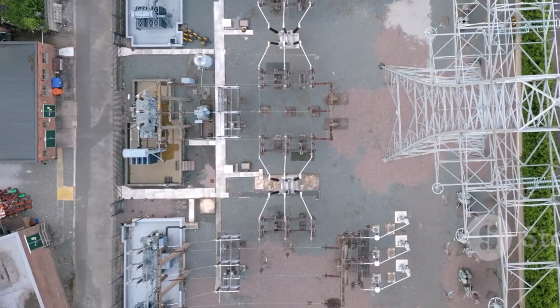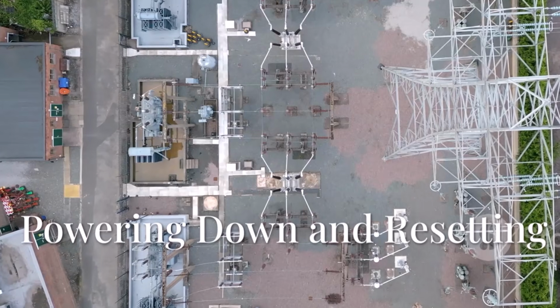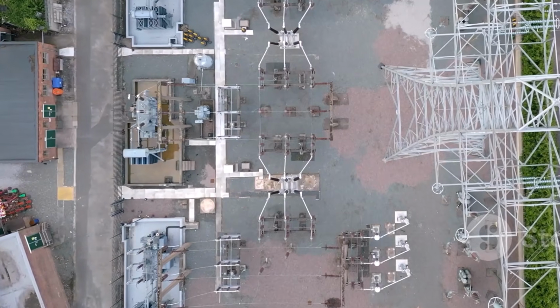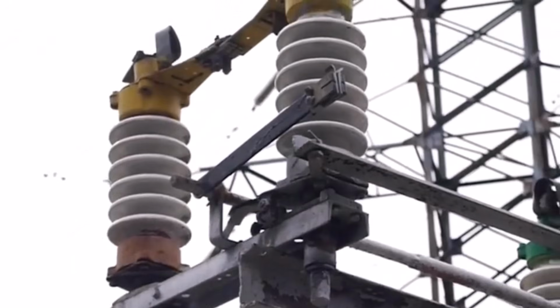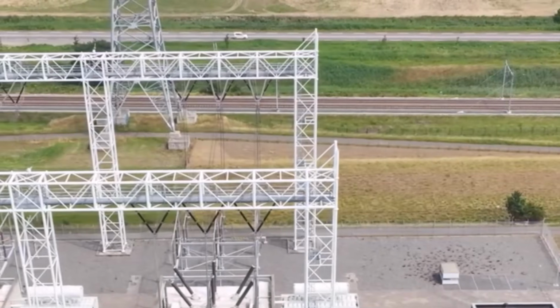Shutting down is as crucial as powering up. First, turn off the load, watch the ammeter drop to 0, and trip the main circuit breaker to de-energize the transformer.